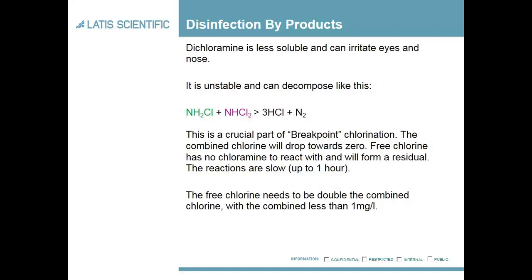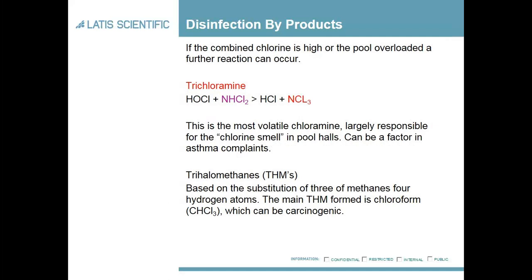As long as the free chlorine has no chloramine to react with, this will form a residual. These reactions are quite slow and can take up to an hour. For this to happen it's key that the free chlorine needs to be at least double the combined chlorine level, with the combined chlorine less than one milligram per litre. If the combined chlorine level is higher than this or if the pool is overloaded, a further reaction can happen in which the dichloramine can form trichloramine.